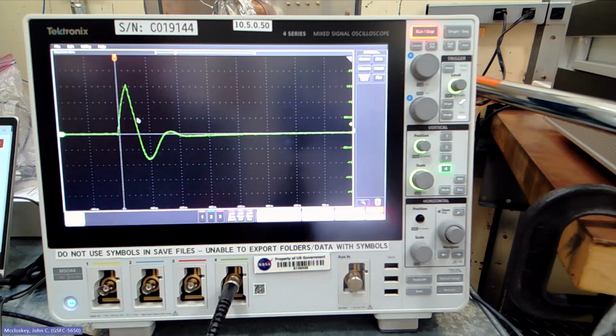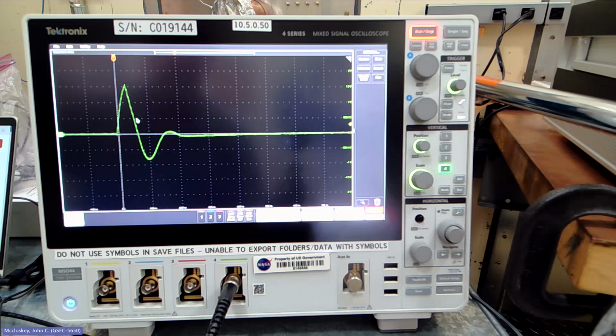But the specifics are less important than just the general observation that these waveforms are likely to look very different from that nice square wave or that nice rectangular pulse that you get in the calibration fixture into that controlled impedance. And that's okay, that's expected. So I just wanted to show you these couple of examples of how different that can look. And when you hook into a real cable in your test configuration, it may look different still. But you can still find some salient characteristics that can help you make sense out of what you're seeing.